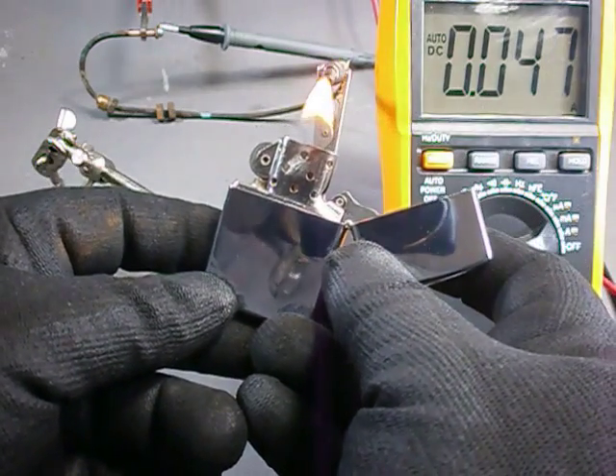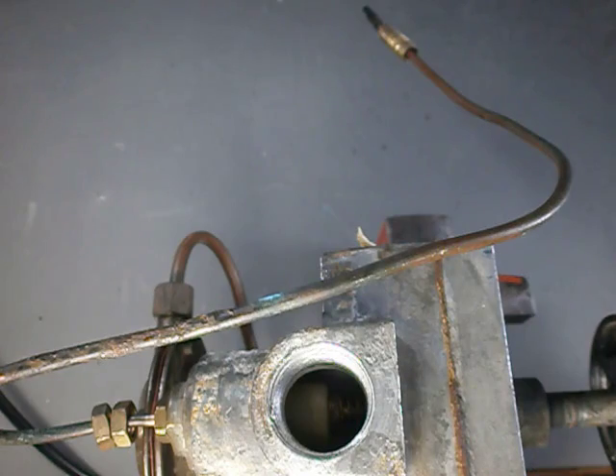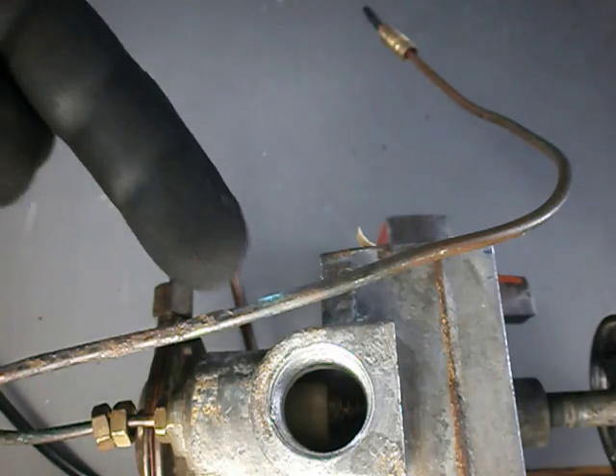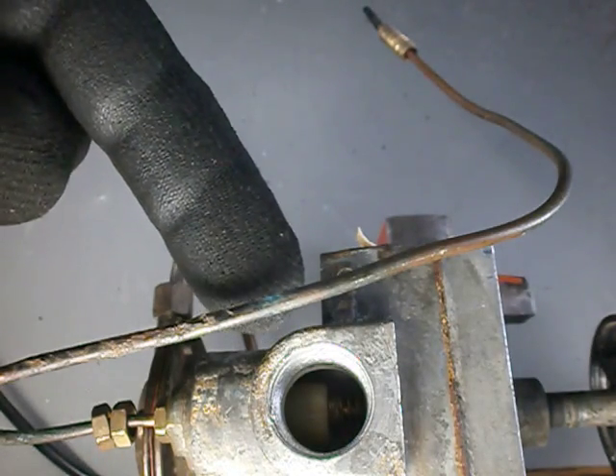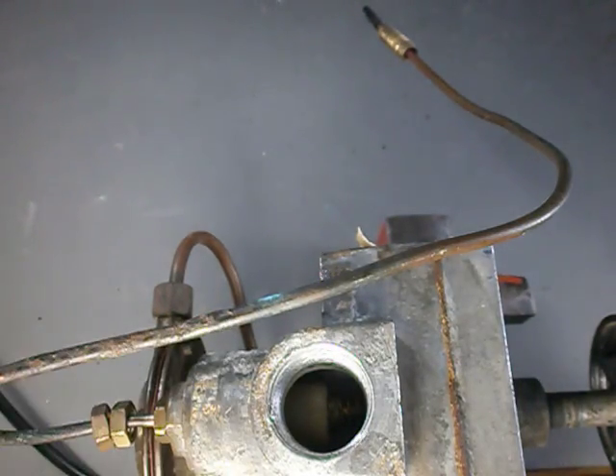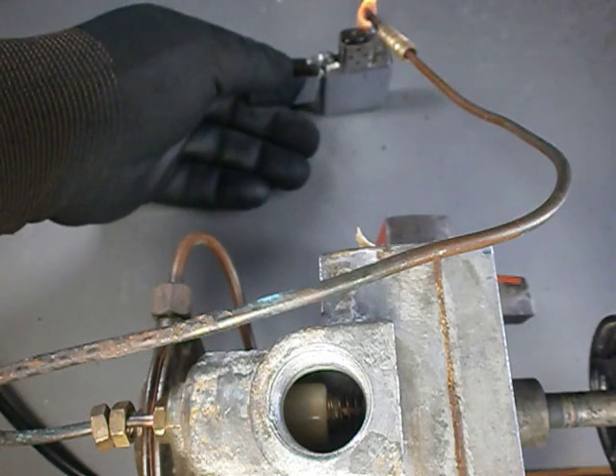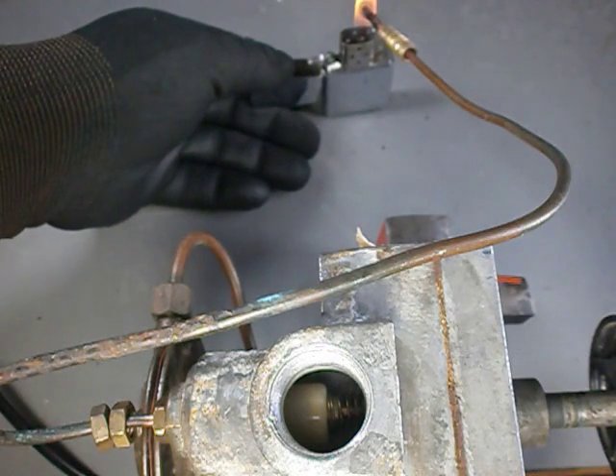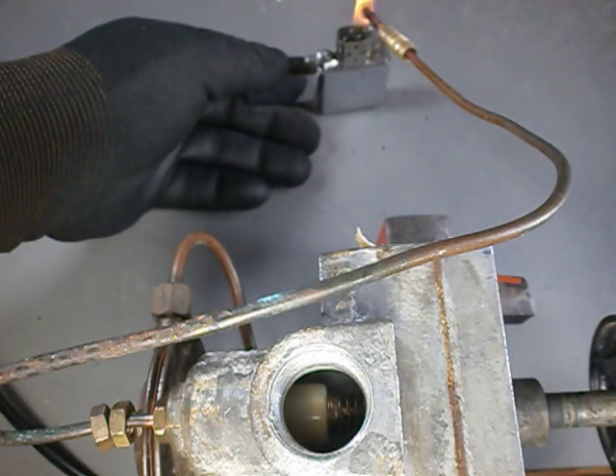Now the thermocouple is firmly attached to the old safety valve and you can see the electromagnet there, and the spring that maintains the valve closed. I am going to light the pilot and see what happens. Well, after almost 20 seconds nothing happened.